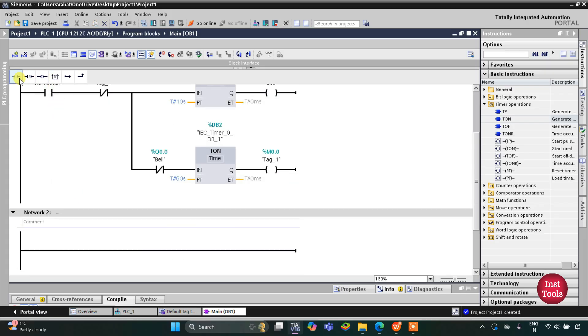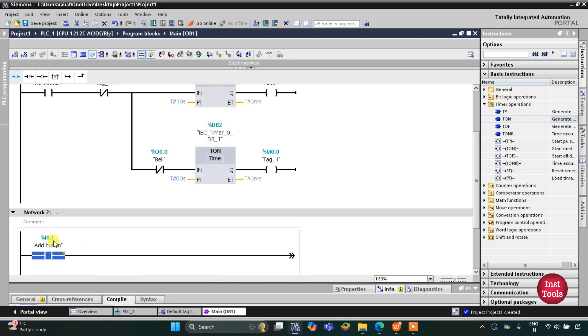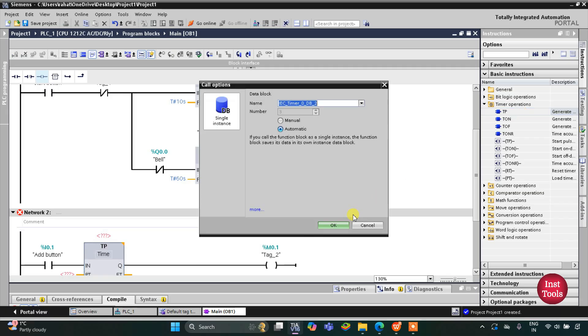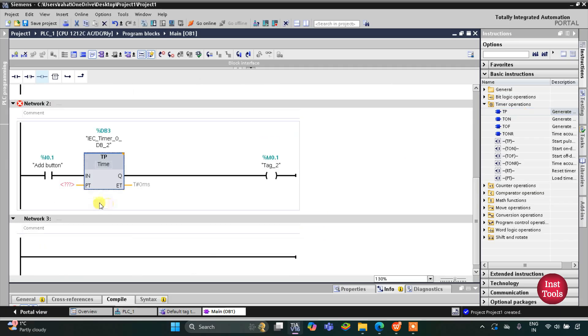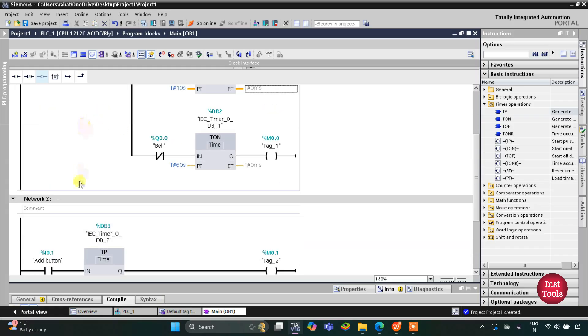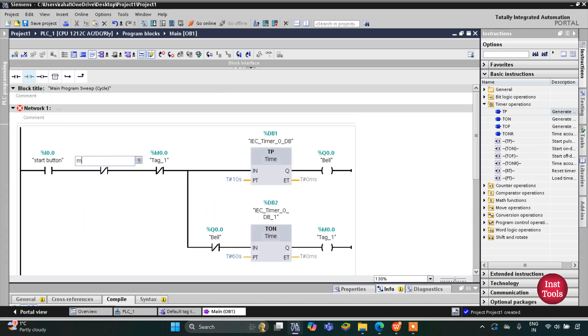In another network, I will use the add button as a normally open contact and then insert a coil for one more memory bit. This memory bit M0.1 should get on for 15 seconds, so we will use a TP timer here with a preset value of 15 seconds. This M0.1 will then be used as a normally closed contact in the first network.